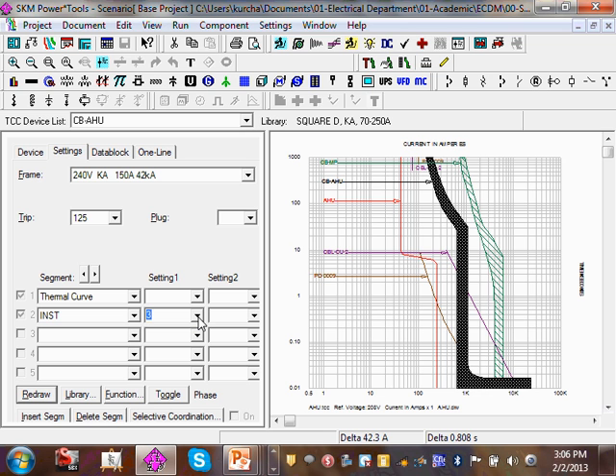You're familiar with adjustable circuit breaker instantaneous with a screwdriver. You can set it at 5, or you can set it at high. And the more you go to the right here, the more energy you're allowing to sit in your equipment, right? So that's what the overcurrent protection coordination will mean. Any comments, guys? Any questions about this?